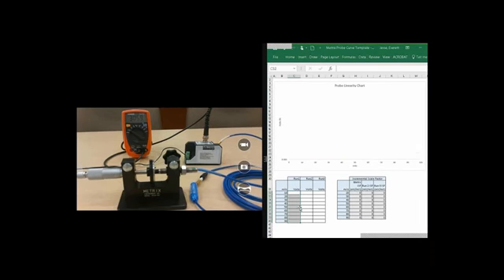We will plot 10 mil voltage increments from 10 mils to 90 mils. The proximity probe scale factor is 200 millivolts per mil. So a 10 mil change will produce approximately a 2 volt change in voltage. You will notice that the line created by the points is very straight, and the slope is very close to 200 millivolts per mil, which is well within the 200 plus or minus 10 millivolts per mil range required by API 670. The incremental scale factor, the slope between points, is also between 190 to 210 millivolts per mil as required by API 670.